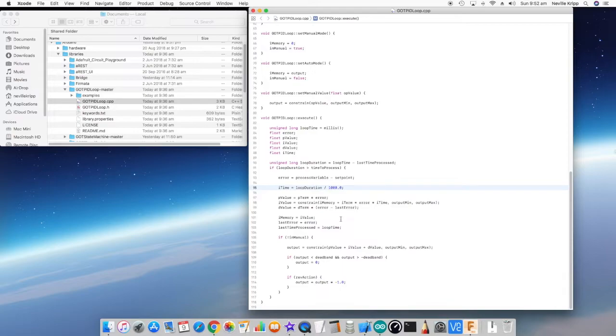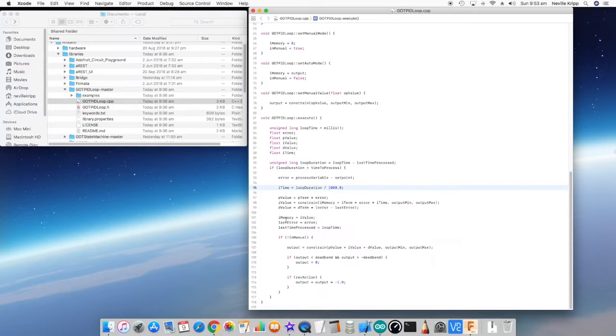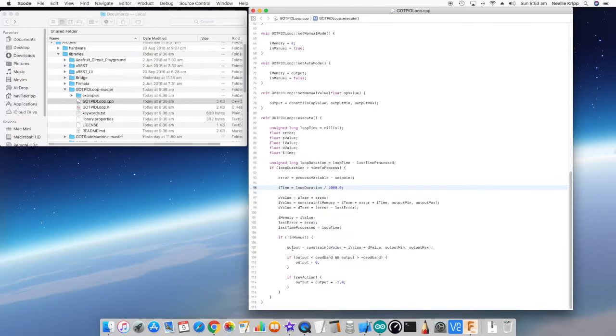The d value is simply the d term times the difference in the error from the last time it processed till now. The i value that was calculated is saved as i memory. The error is saved as last error, and the loop time is saved as the last time it was processed. Then we actually do a check to see whether the loop is in manual.